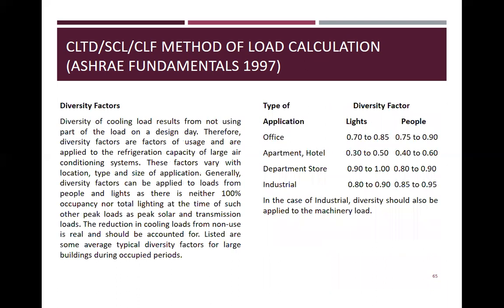Diversity factor. Diversity of cooling load results from not using part of the load on the design day. Therefore, diversity factors are factors of usage and are applied to refrigeration capacity of large air conditioning systems. These factors vary with location, type, and size of application. Generally, the diversity factors can be applied to loads from people and lights, as there is neither 100% occupancy nor total lighting at the time of such other peak loads as peak solar and transmission load. The reduction in cooling loads from non-use is real and should be accounted for.